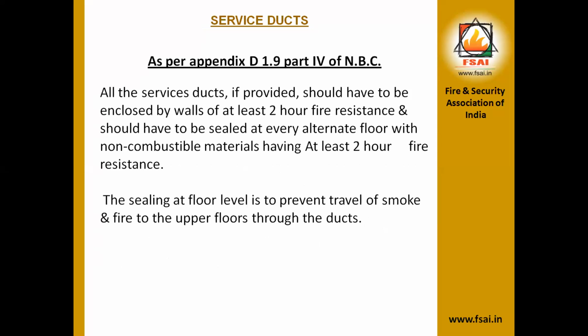All the service ducts, if provided, should be enclosed by walls of at least 2 hours fire resistance and should be sealed at every alternate floor with non-combustible material having at least 2 hours fire resistance. The sealing at the floor level is to prevent the travel of smoke and fire to the upper floors through the ducts. The next is the water tank.